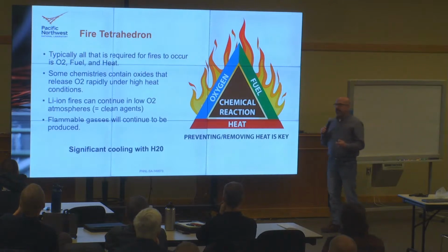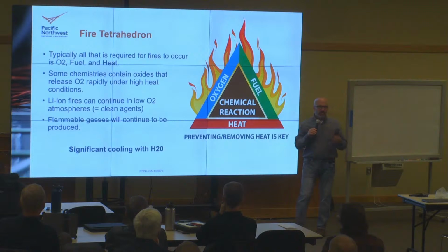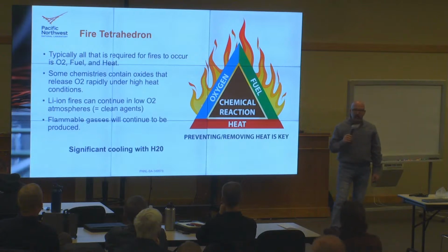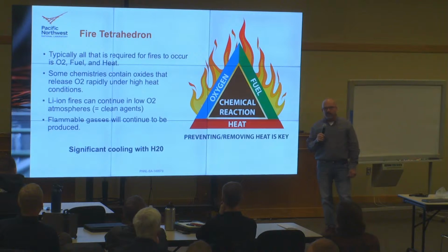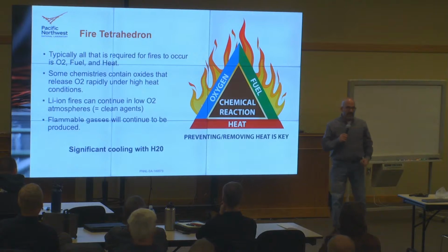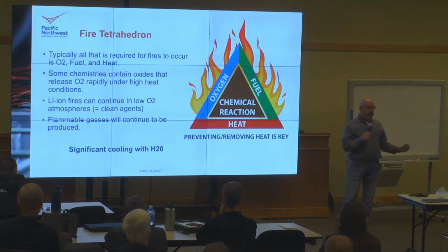It should be kind of obvious at this point that there is no holy grail when it comes to fire suppressant agents. There really isn't. You'll see marketing out there from different clean agent manufacturers and aerosol manufacturers, and they're even putting them in energy storage systems, selling them as fire suppression for the battery. They're fire suppression for visible flame. All of those agents work great on visible flame, but not on deep-seated battery fires.